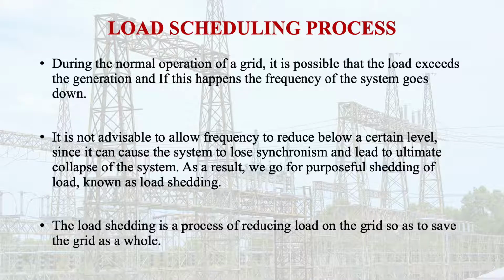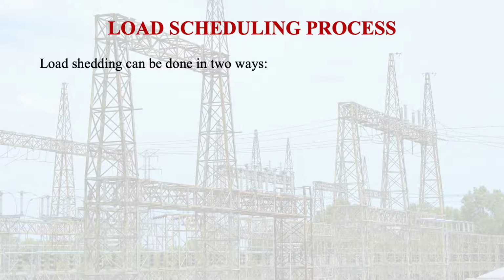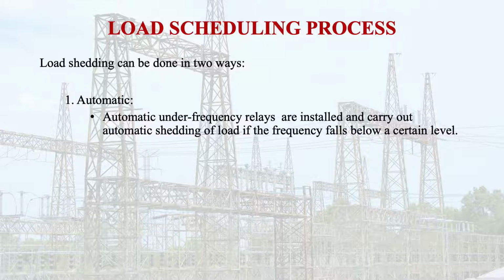Load shedding is the process of reducing the load on the grid. By cutting the load, we are reducing the load on the grid so as to save the grid as a whole if the demand is high. Load shedding can be done in two ways. It can be automatic, or manual load shedding is also possible. For automatic load shedding, automatic under-frequency relays are installed. Under frequency relays, you have heard about this.